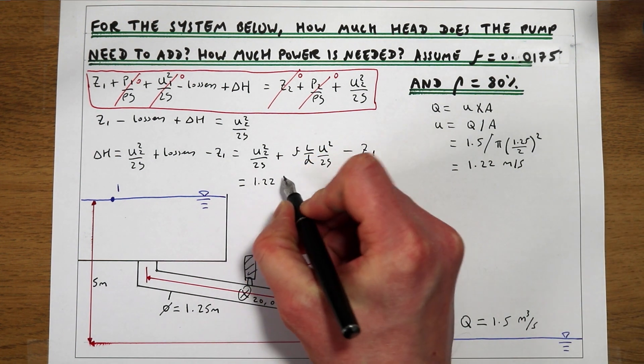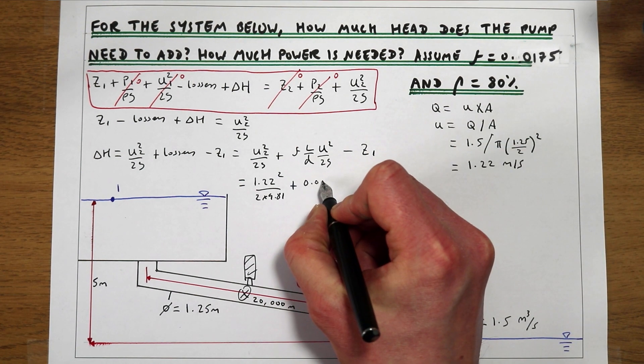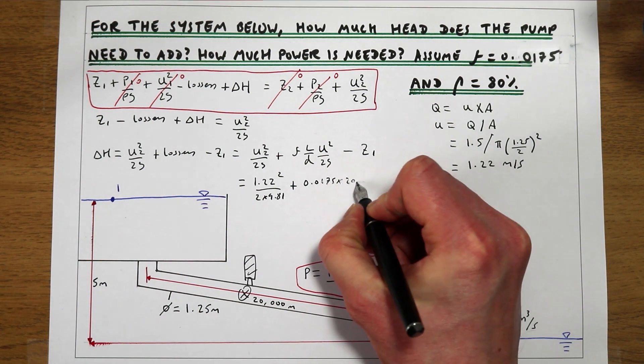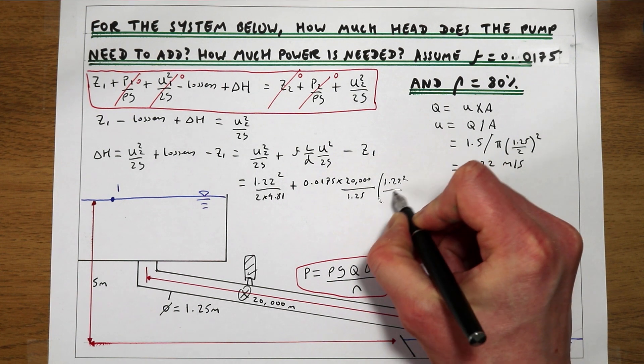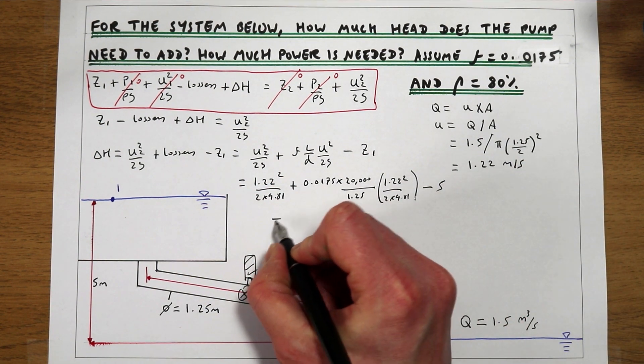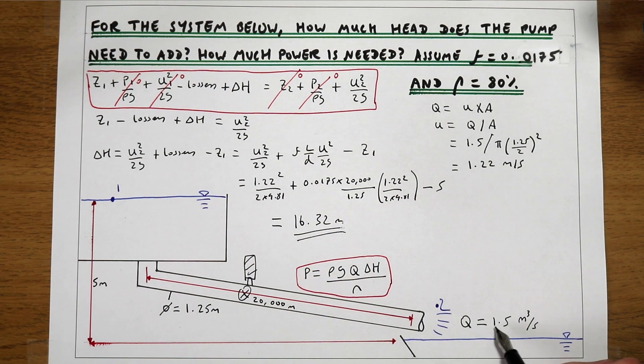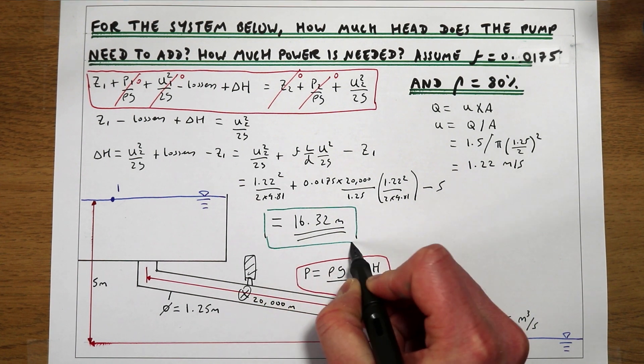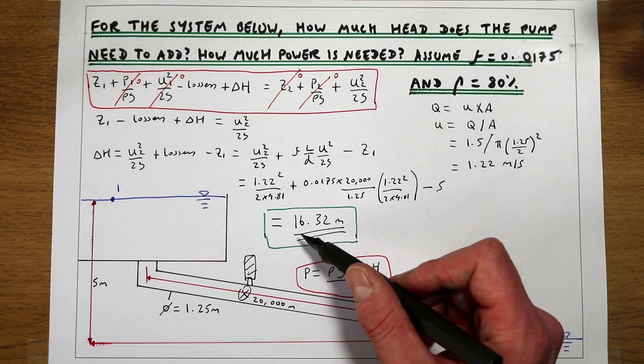We now have everything needed to plug in the numbers: velocity 1.22 m/s, friction factor 0.0175, pipe length 20,000 m, pipe diameter 1.25 m, and Z1 equals 5 metres of elevation. This tells us the pump needs to add 16.32 metres of energy to keep the system flowing at 1.5 m³/s. That is how much head ΔH the pump needs to add to the system to keep it flowing.